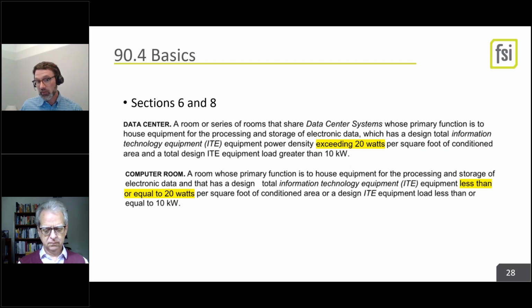I think it's really important to understand what is a data center and what is merely a computer room. That's power density, and that's of the room. You might have a server rack that tops, they're now topping like crazy, 100 watts per square foot. But if you're a computer room, the room could also have post racks, random other equipment, could have a UPS that really doesn't put off that much heat. So in the room, you've got equipment load and a power density that makes you a data center or a computer room. This is straight out of definitions.